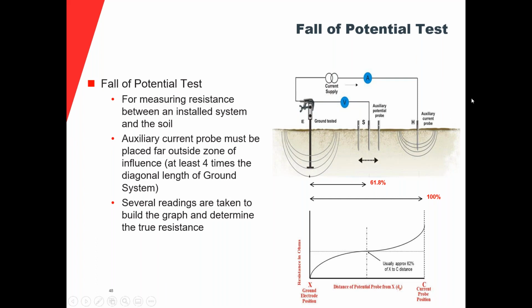Another test is the fall of potential test. So we can do the fall of potential test using the MFT that was presented by Ali. So what it does, you have this electrode here. So you can connect something like this. Okay. So this is the length of your electrode or the test probe. And it must go up to the 61.8% of this distance here. So what it does, it supplies current to the loop. So what is the loop here?